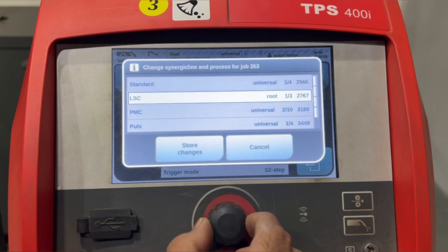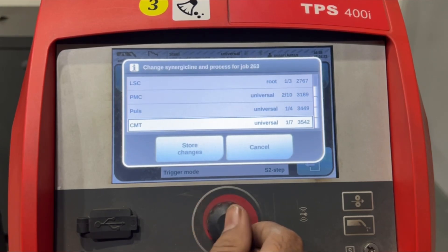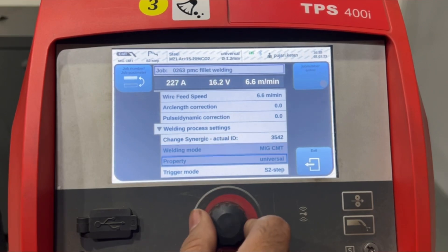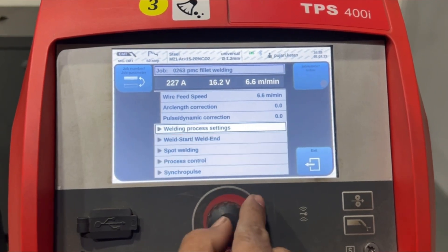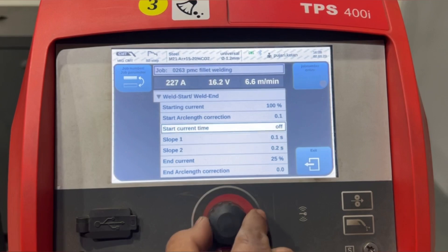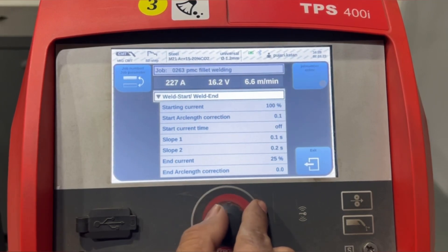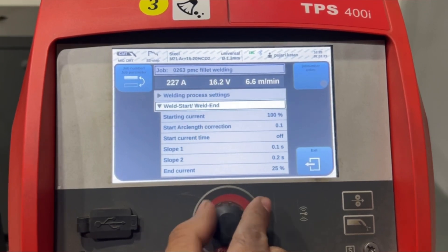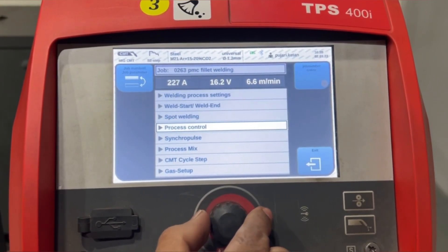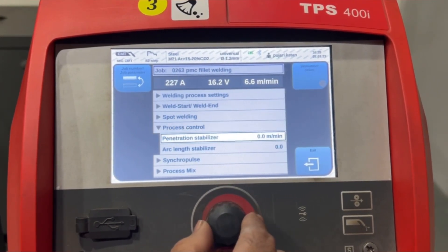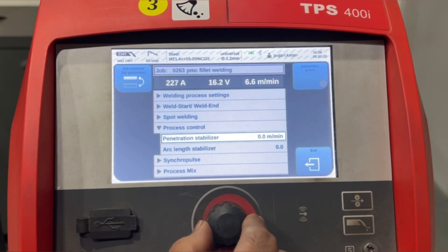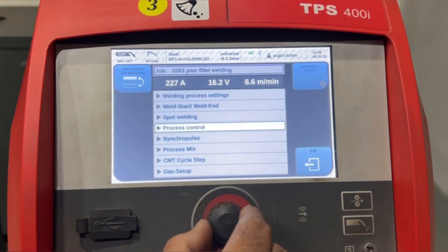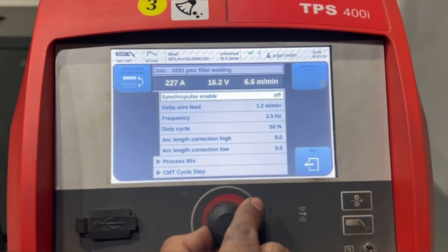If you want to optimize the start and end of the welding, you can do so in the weld start and weld end options. If you are using LSC or PMC, then in the process control option you can turn on the penetration stabilizer. If you want to get ripples in welding, you can turn on the synchro pulse setting.